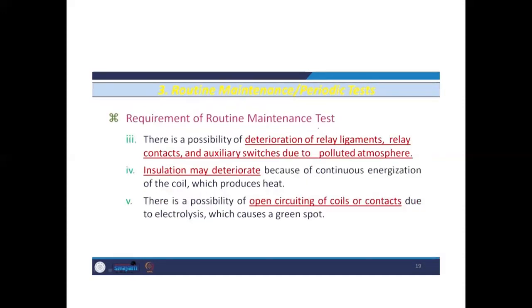Third one is, there is a possibility of deterioration of the relay ligaments, the relay contacts and auxiliary switches due to polluted atmosphere. So these may deteriorate its operation, and they should be checked out. Insulation may also deteriorate because of continuous energization of the coil, which produces heat. The continuous energizing and de-energizing causes heat, which may deteriorate its insulation.